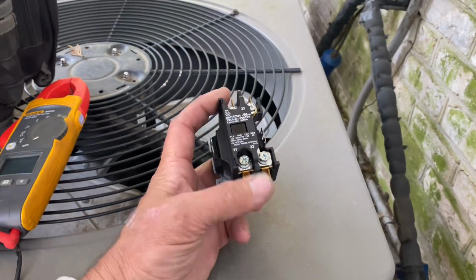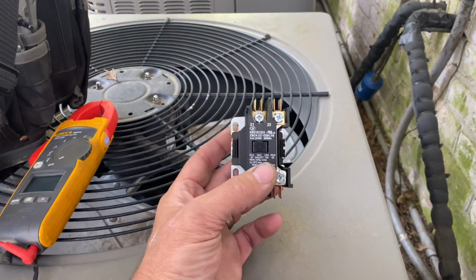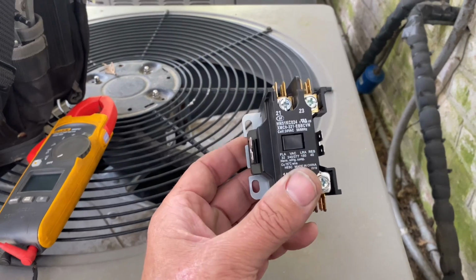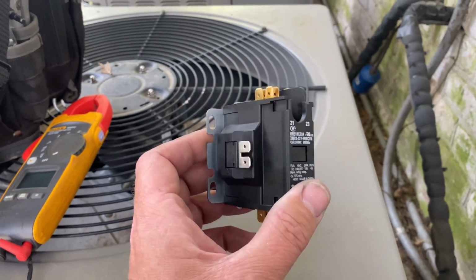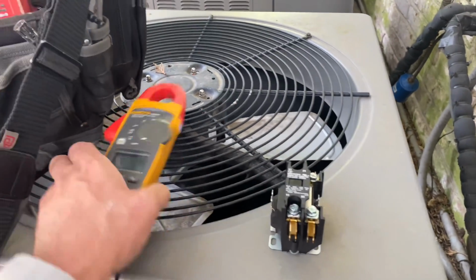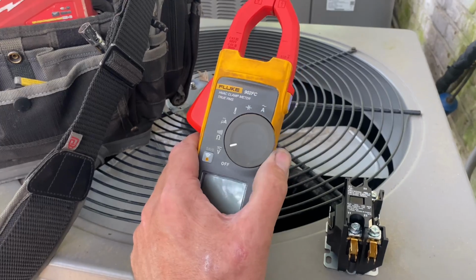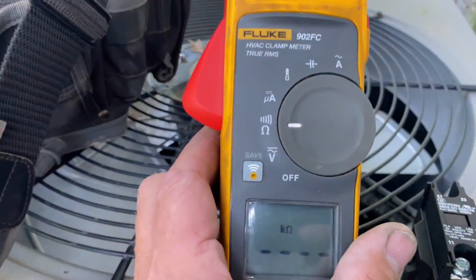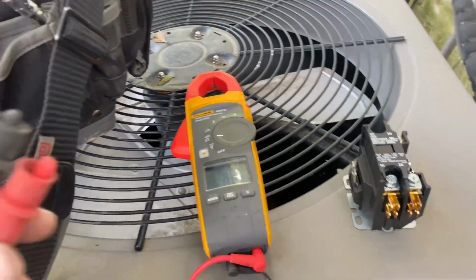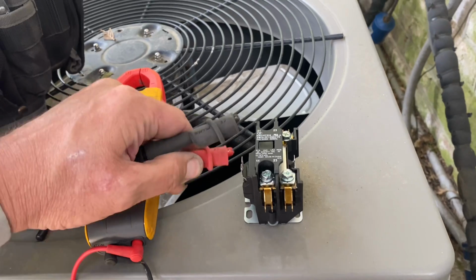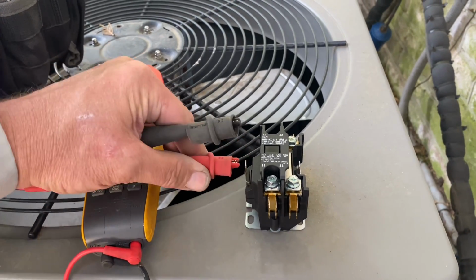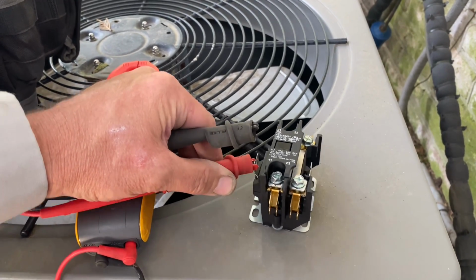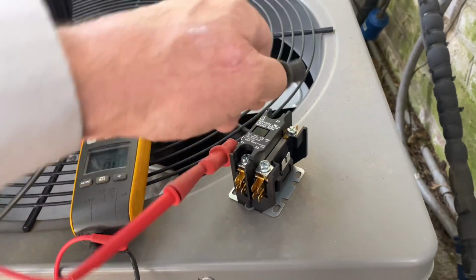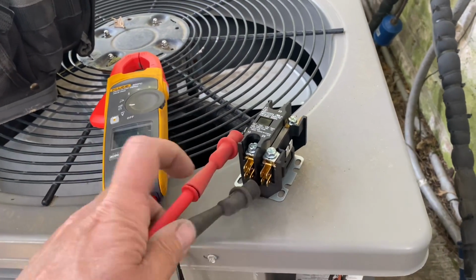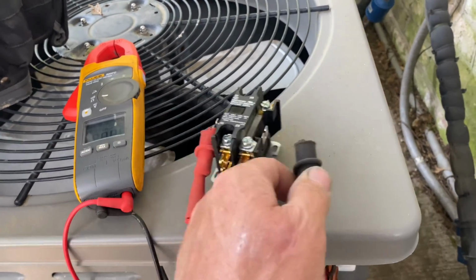Now, I teach my guys, and I was taught as well, that when we're doing a preventative maintenance service call, we always want to test the contactor. And how do you do it? Well, use a multimeter like this that has the ability to read resistance. So we're going to put one lead on one side of the 24 volt coil. I'm trying to do this one-handed, excuse me. And we'll do the other lead on the other side. All right, let's get that on there.